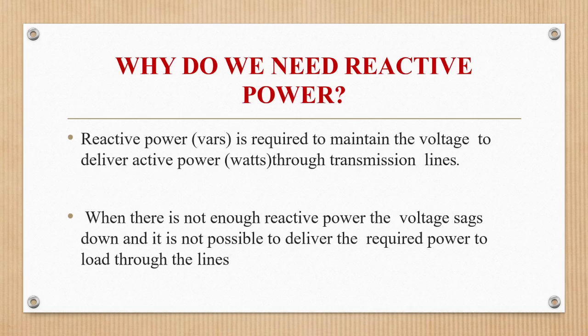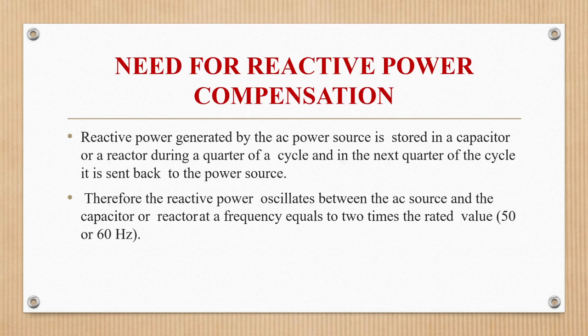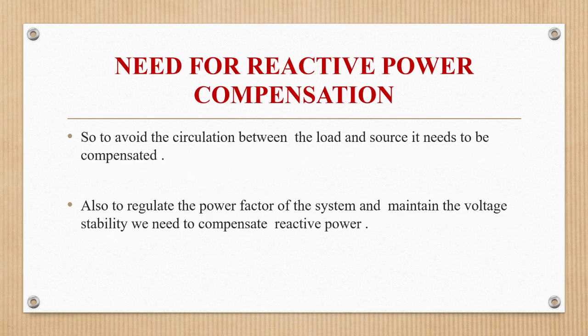Reactive power (volt-ampere reactives) is required to maintain the voltage to deliver active power through transmission lines. When there is not enough reactive power, voltage will sag and it is not possible to deliver the required power to the load. Reactive power generated by the AC power source is stored in a capacitor or reactor during one quarter of a cycle and sent back to the power source in the next quarter cycle. Therefore, reactive power oscillates between the AC source and the capacitor or reactor at a frequency equal to twice the rated frequency (2 × 50 or 60 Hz). To avoid this circulation and to regulate power factor and maintain voltage stability, reactive power needs to be compensated.